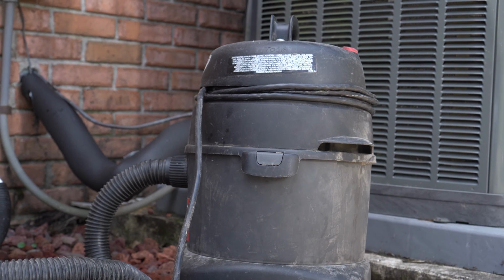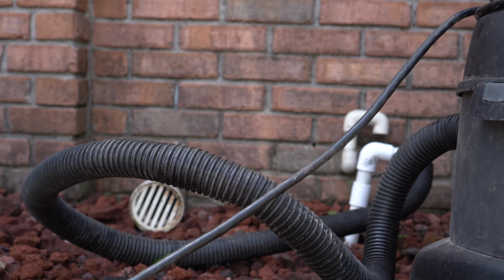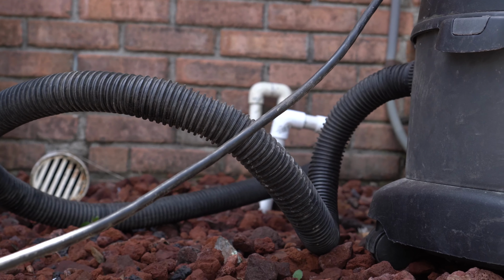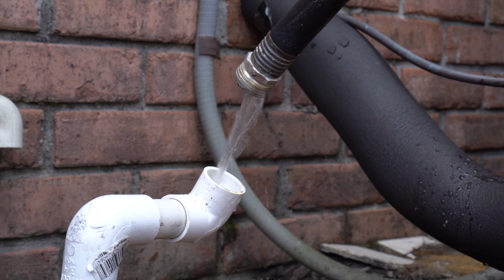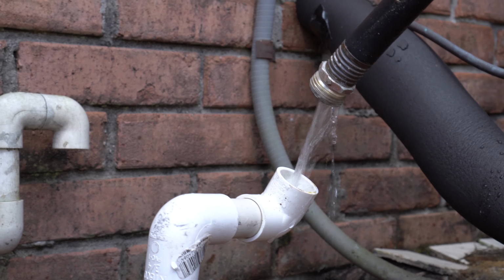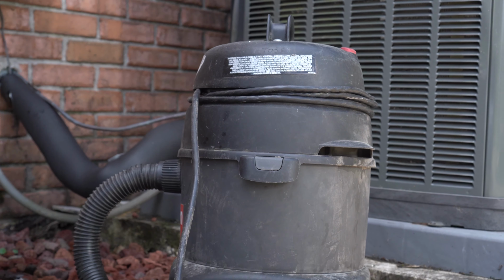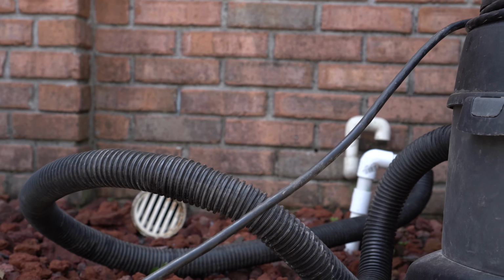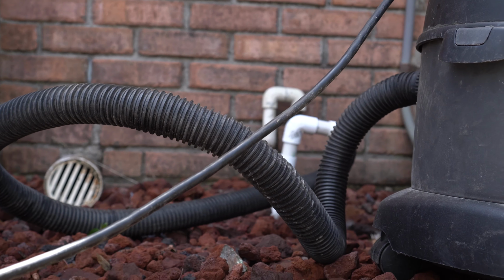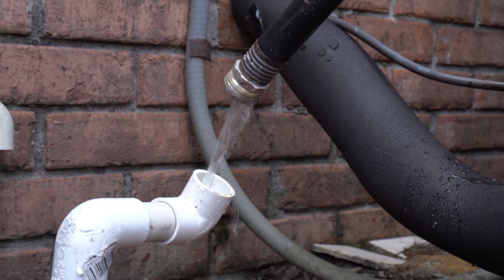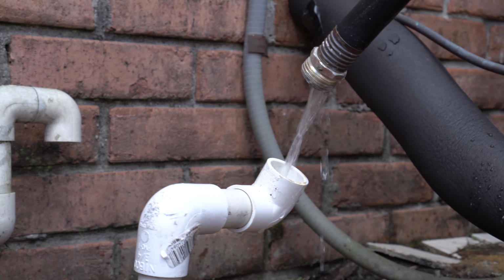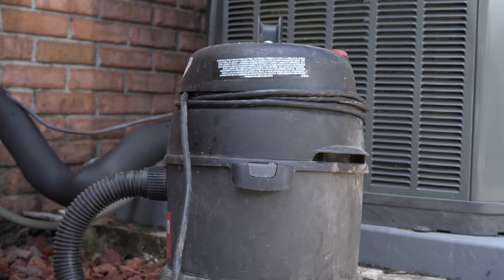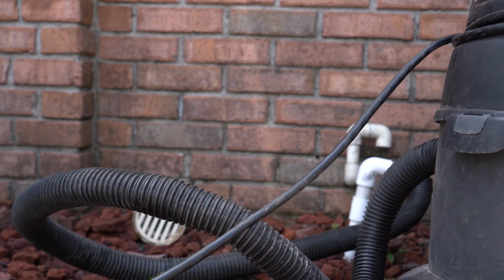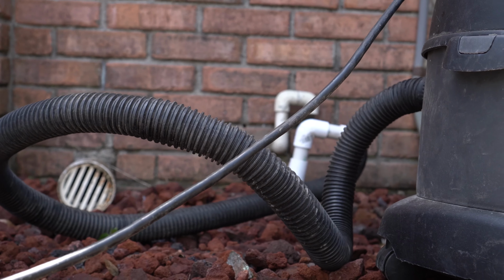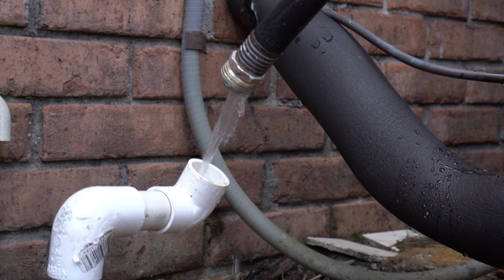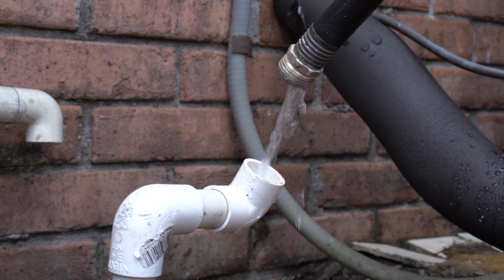Standard operating procedure during air duct cleanings is to clean the primary drain line of the client's HVAC system. Depending on the configuration of the drain system, water may need to be added back to prime the trap. We recommend cleaning the drain line prior to cleaning the coil so that the water used to clean the coil will automatically prime the trap, saving an additional step. If you clean the drain line after the coil cleaning, make sure you add a half gallon of water back to the drain system to prime the trap. If the trap is not primed, the unit will not drain, causing water to leak and damage the customer's home.